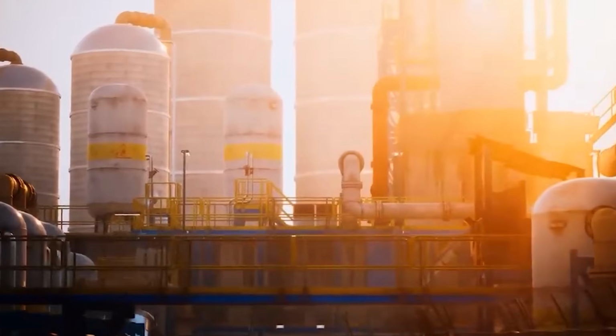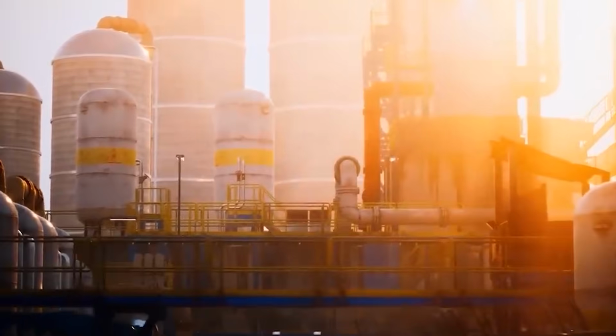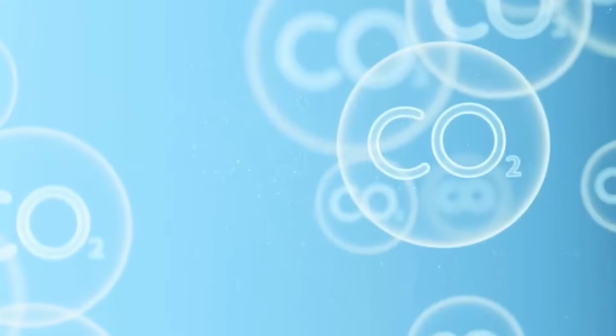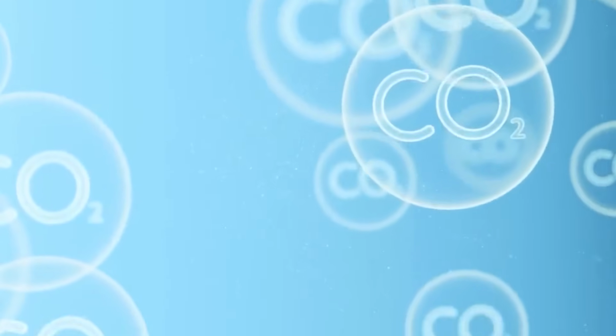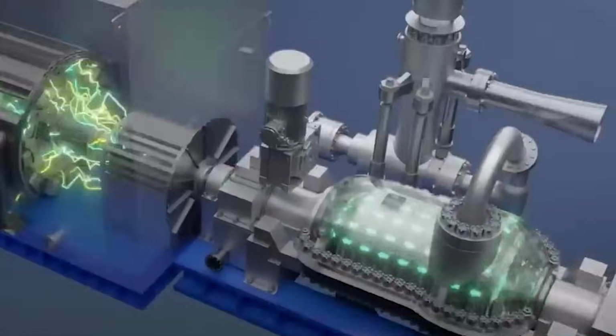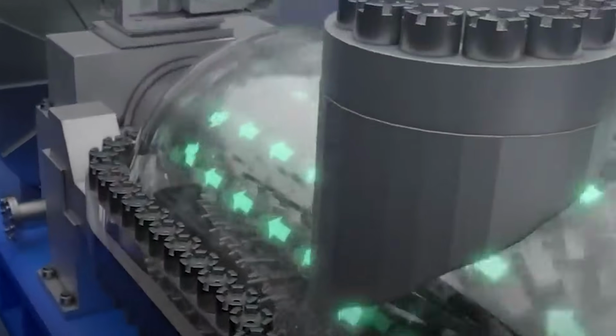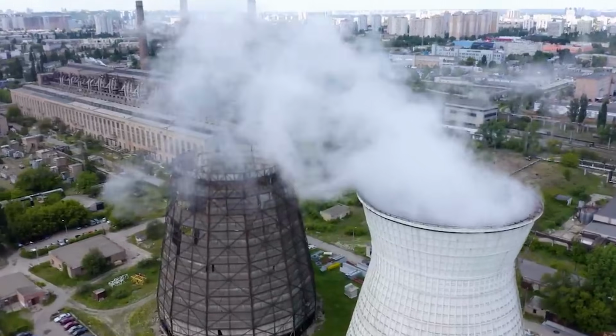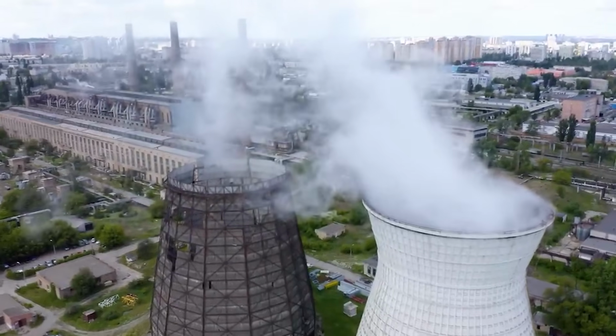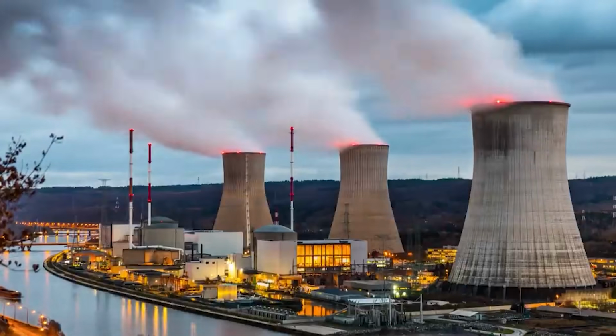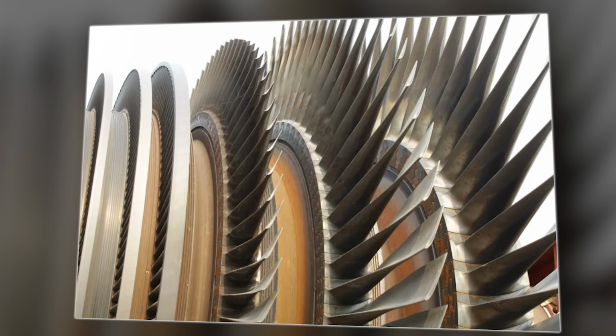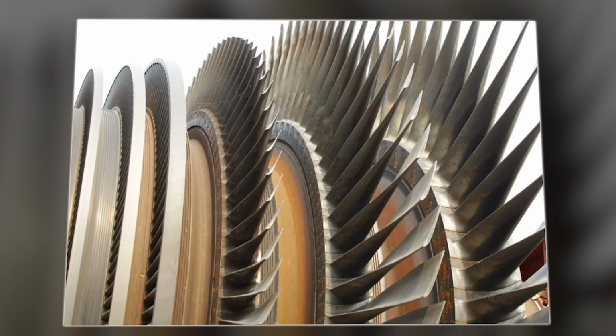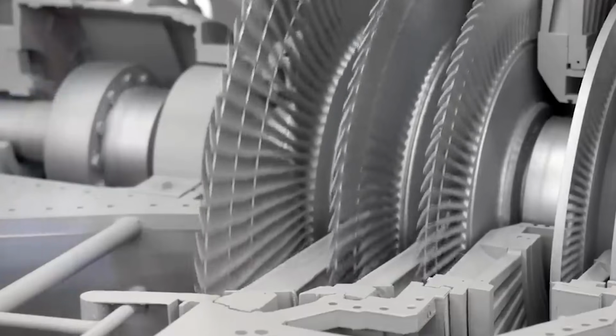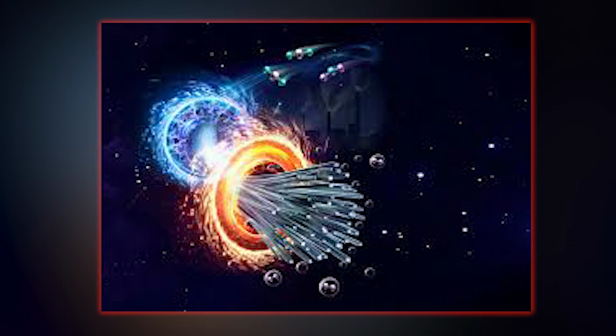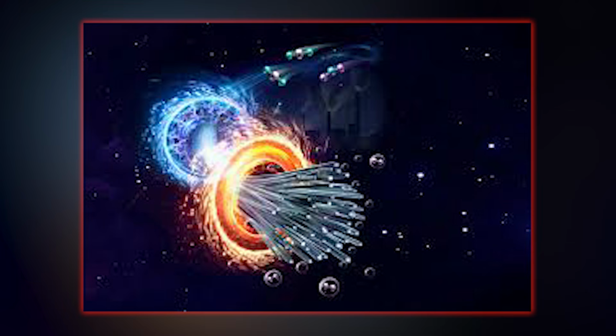And then you try to build the machine. And the machine tries to destroy itself. The first problem is the CO2 itself. At supercritical temperatures, we are talking 600, 700 degrees Fahrenheit, and above, carbon dioxide stops being chemically passive. It becomes aggressive.